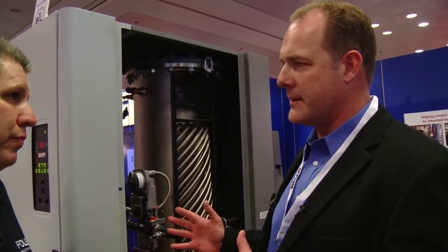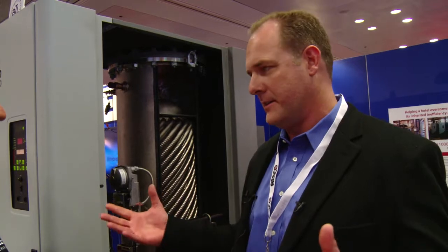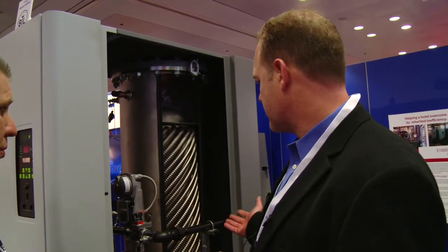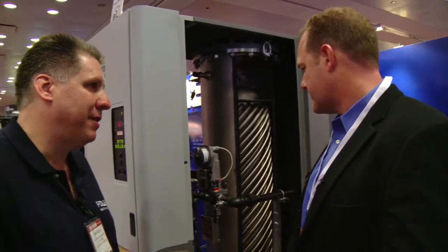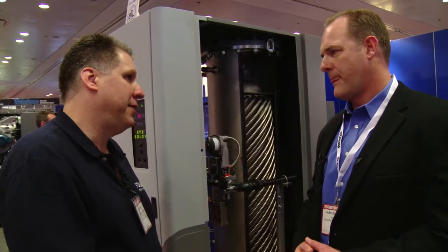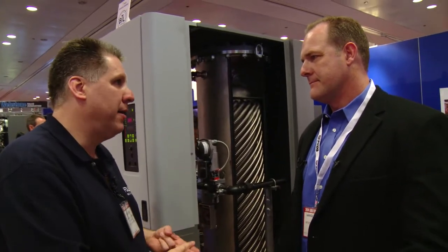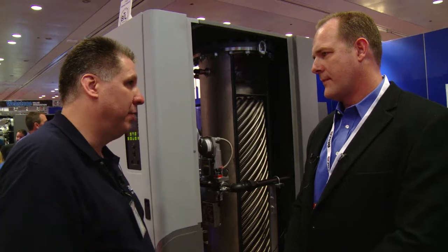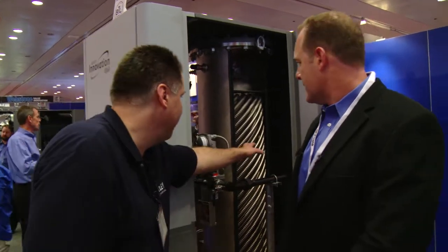So the great thing about this is not just its ease of installation as far as footprint and being able to retrofit buildings that have those large storage tanks that eventually fail over time, but also the ability to not apply it with any storage tanks. So the ease of installation and the footprint that it takes in most mechanical rooms is much simpler and much smaller. Well, that's a huge plus, because mechanical space obviously is at a premium. Absolutely. Storage tanks take up space, they leak, they're hard to get in and out, so this simplifies it considerably. Talk about this heat exchanger. What's this heat exchanger made out of?